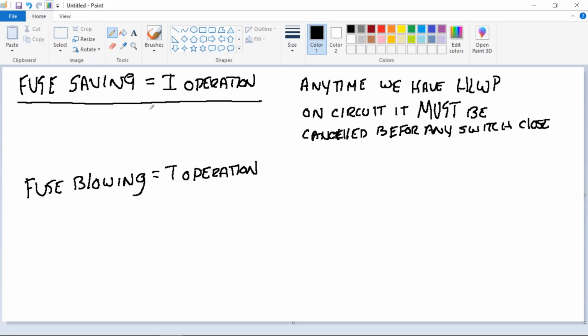All right. Once again, we're talking fuse here, so we're not talking about disconnect switches. We're talking about fuse switches or any fuse type situations. When we did the capacitor bank and we went through those steps, we opened the fuse cutouts. Say we had a hotline work permit on the circuit. What do we need to do before we close the fuse cutouts in that step? Cancel the permit. Cancel the hotline work permit.